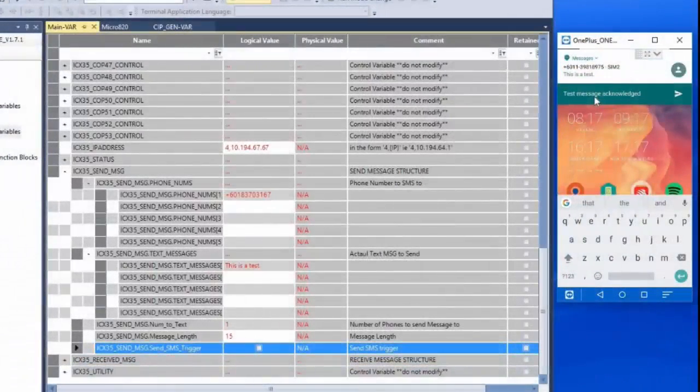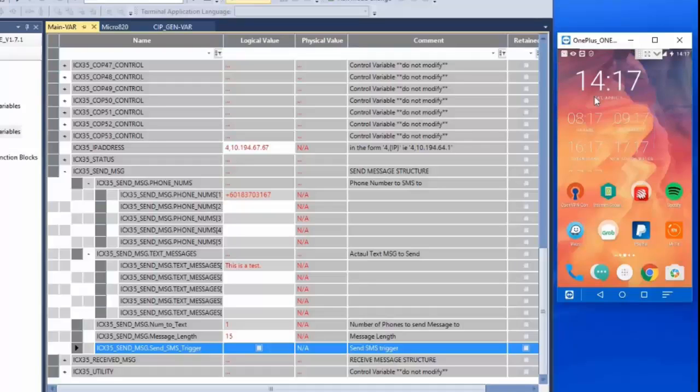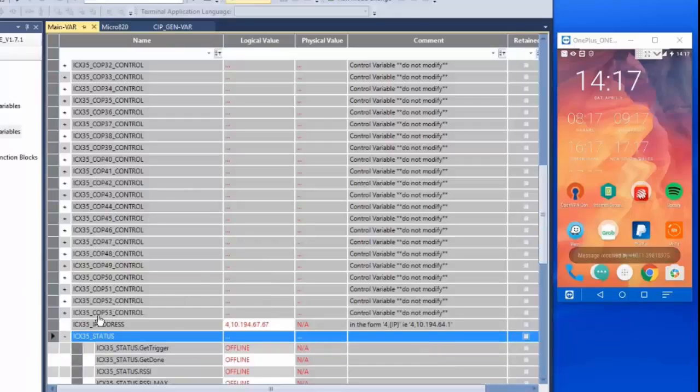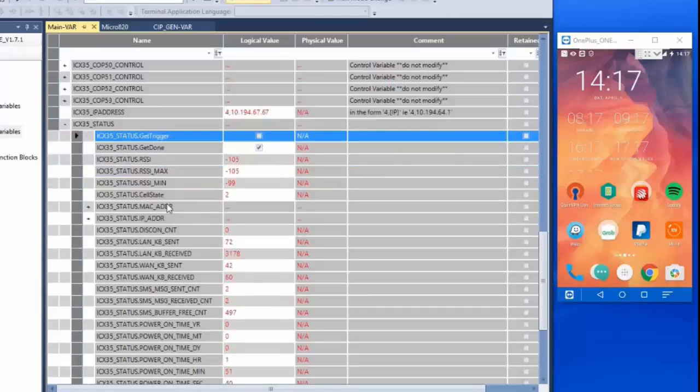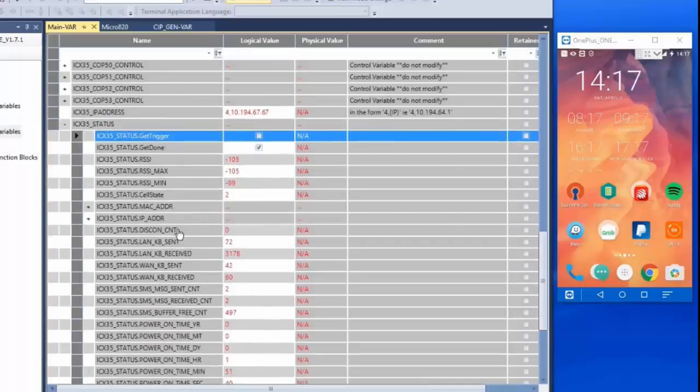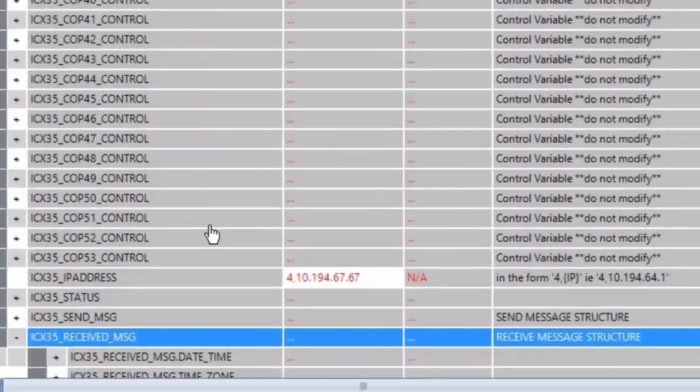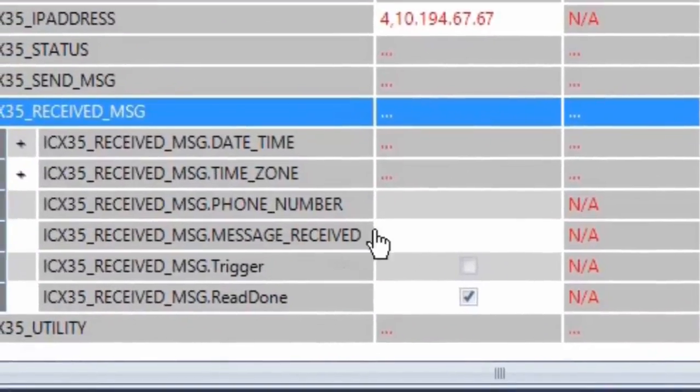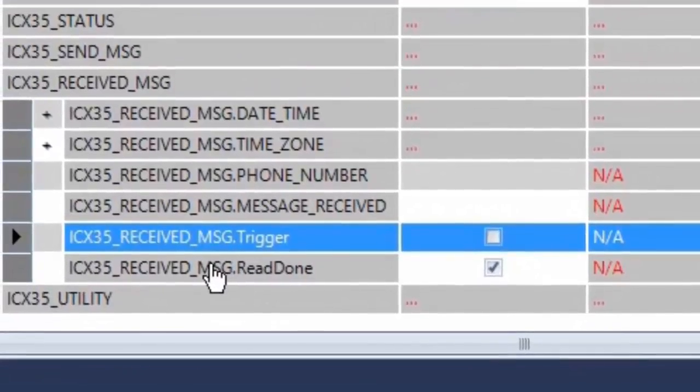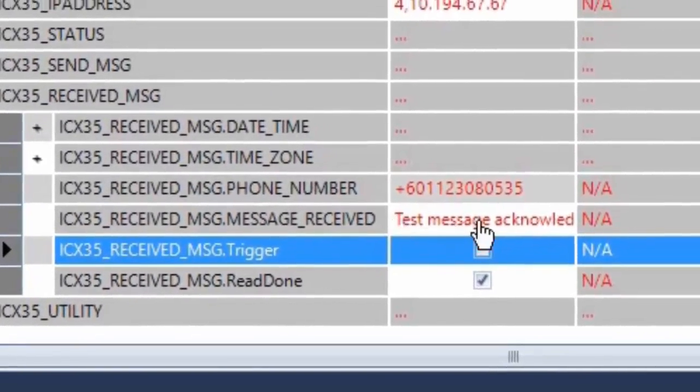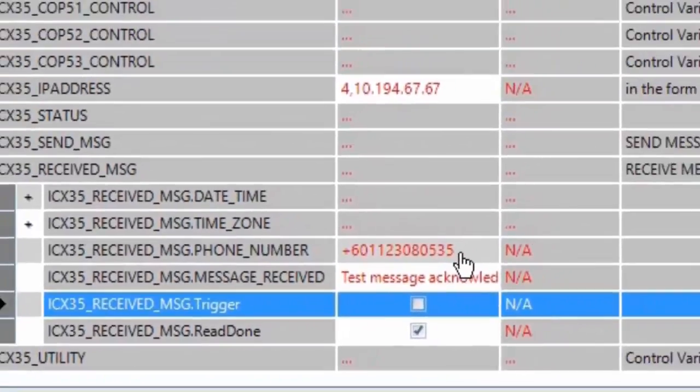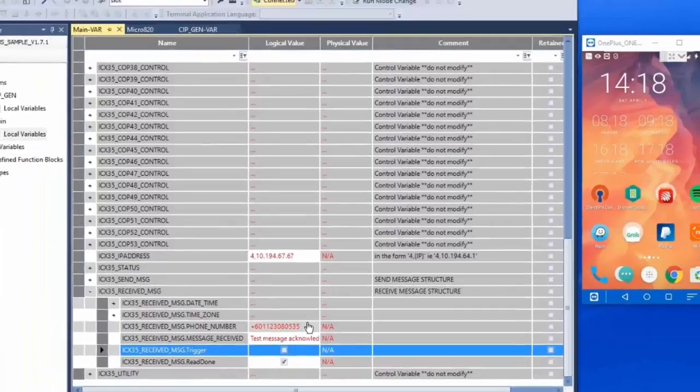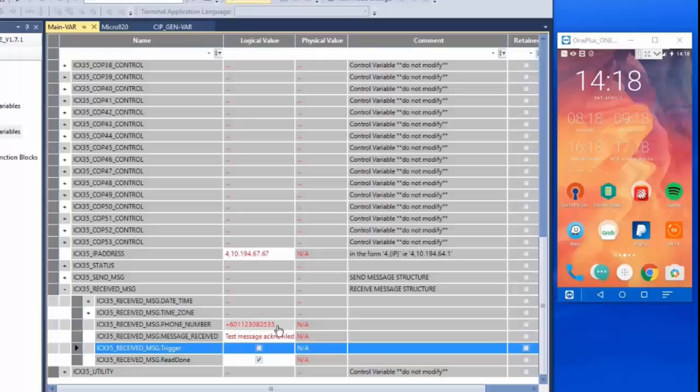And the reply will show up in our received message tags. And in addition, we can also look at the status tags to see that the messages sent counter has gone up as well as the messages received counter once we get the reply. Something to note: as messages are received by the ICX35, it does not simply send them on to the controller. They're actually stored in a buffer on the gateway. So to get the reply messages in the tags, we must send a high signal to the received message trigger boolean tag. This will send an instruction to the ICX35 to write the content of the SMS messages received as well as the corresponding phone numbers to our Micro 800 controller. And we'll then be able to see them in the message received tags.